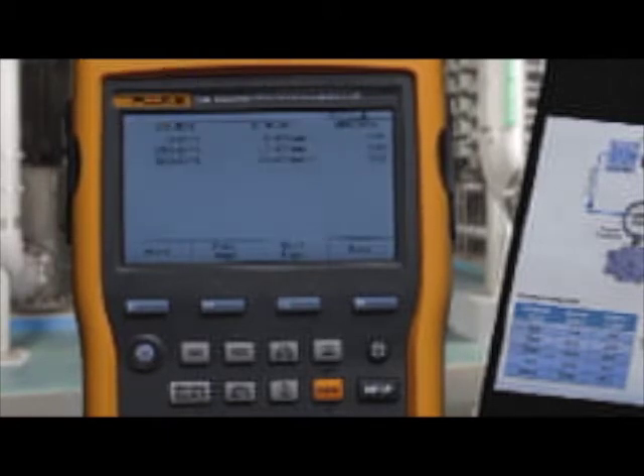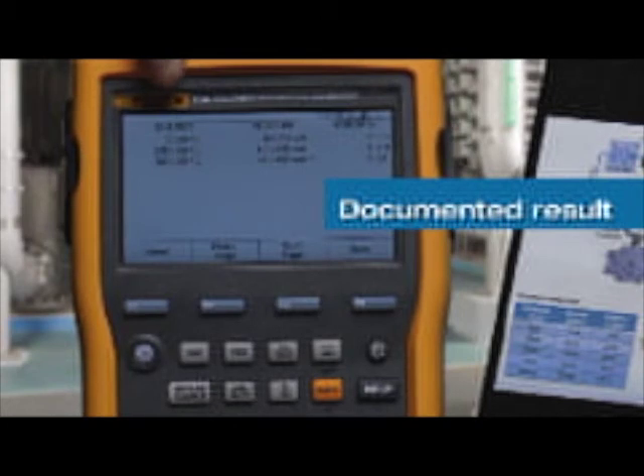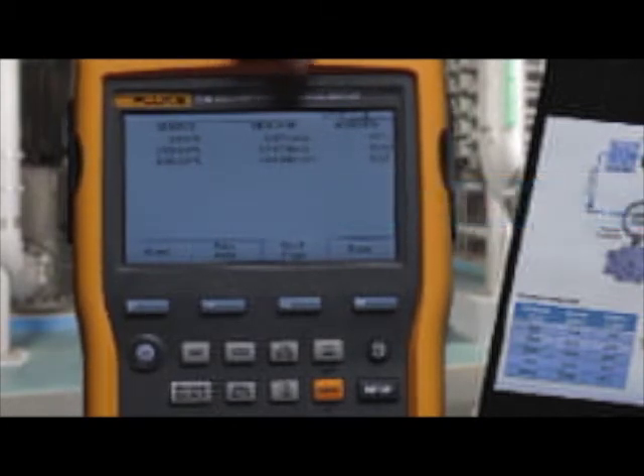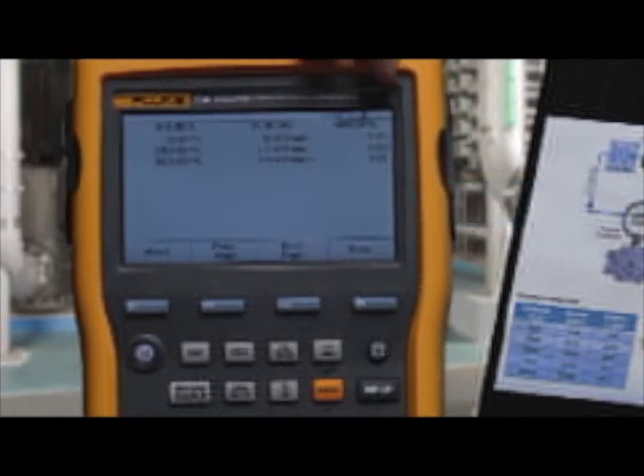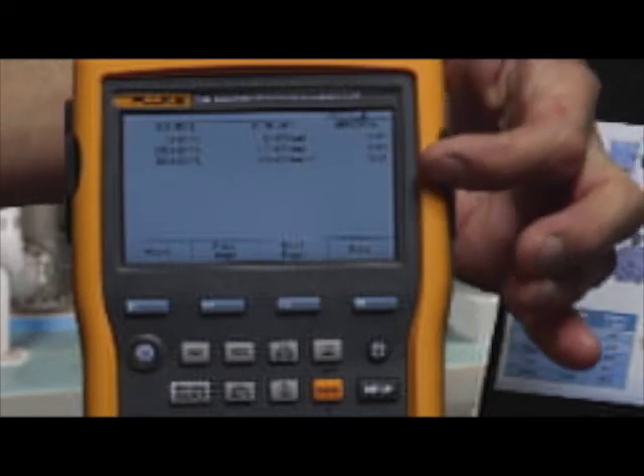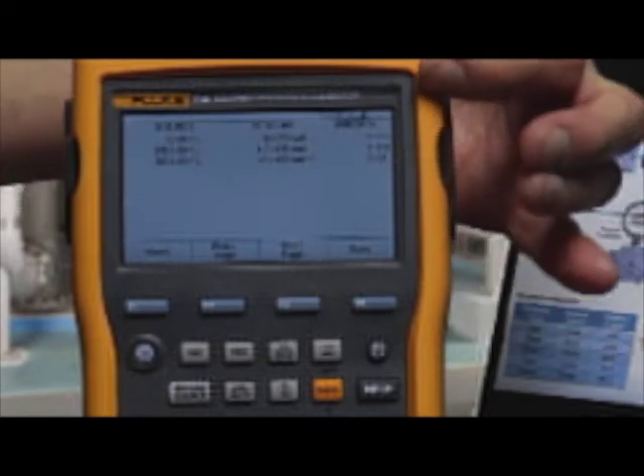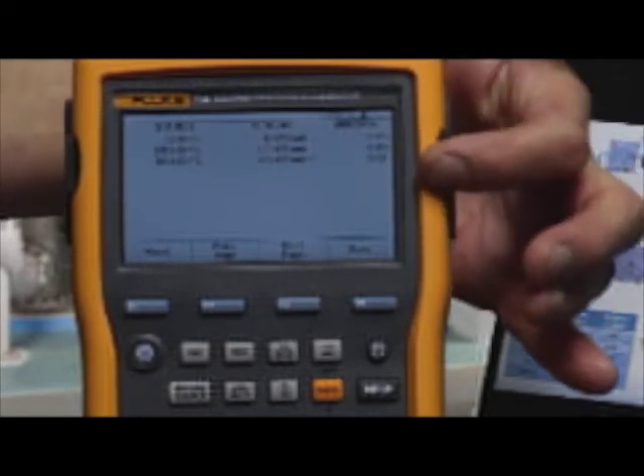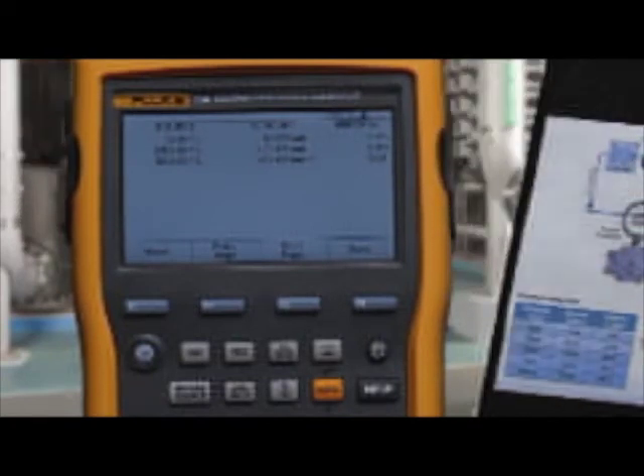When the test is done, you have the documented applied temperature, measured current, and error percent of span for each point. None of the error percents are in reverse video, indicating that all the milliamp measured values were within the allowable test tolerance, and the transmitter passes the calibration test.